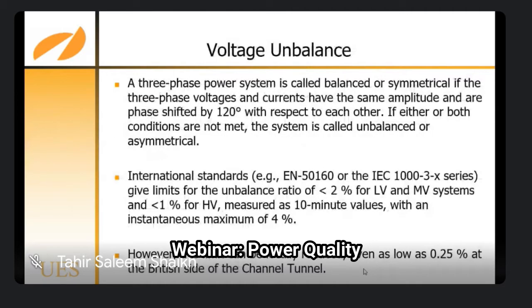That is also very important: the voltage unbalance. A three-phase power system is called balanced or symmetrical if the three-phase voltages and currents have the same amplitude and are phase shifted by 120 degrees with respect to each other. If either or both conditions are not met, the system is called unbalanced or asymmetrical. And this is a big problem for the maintenance people.